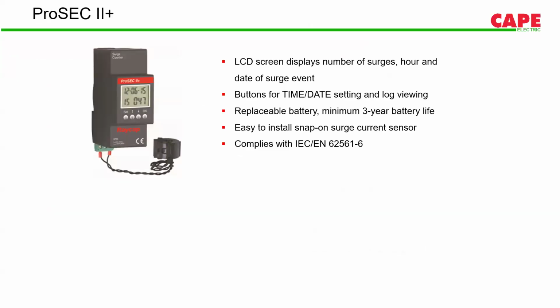So these are the surge counters. SPDs are parallel connected devices, and they do not trip like MCBs. Whenever there is a fault current, an MCB trips, whereas nothing like that happens to an SPD. During the surge, the SPD will operate, and after the surge it will regain its original position. Then how do you know that there was a surge? You can install a counter next to an SPD, which will give you the date and time of the event. It will log up to 999 events, and then it can be reset.